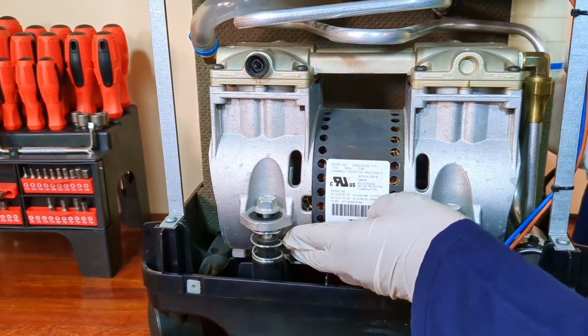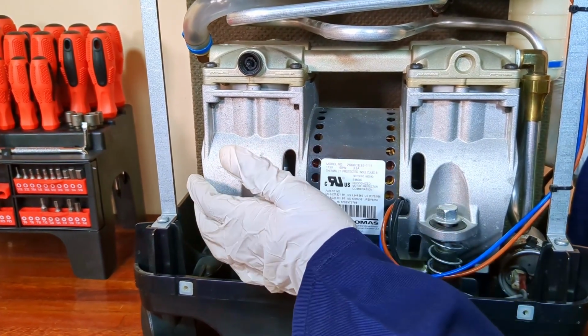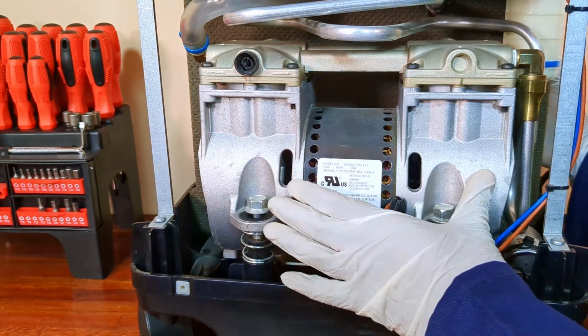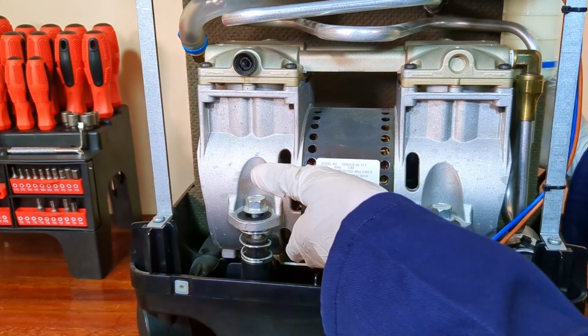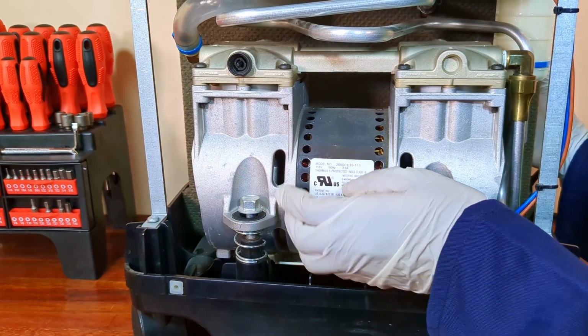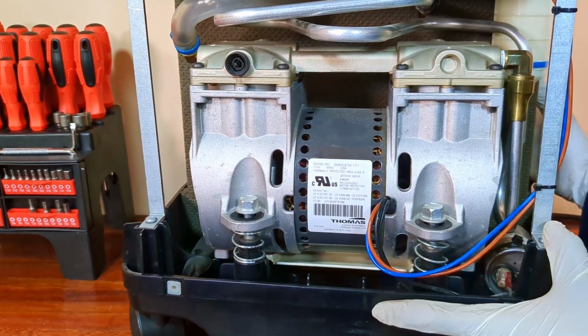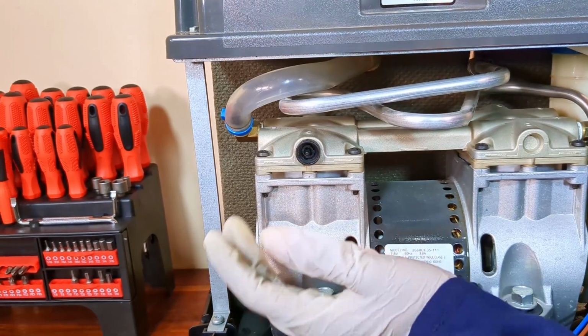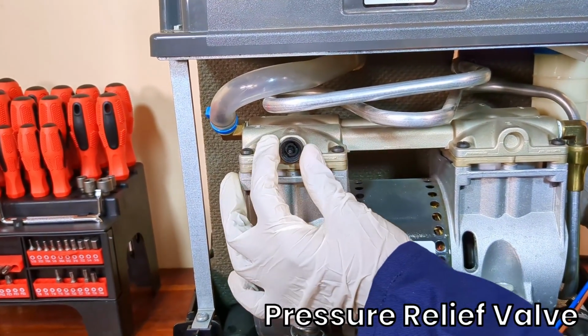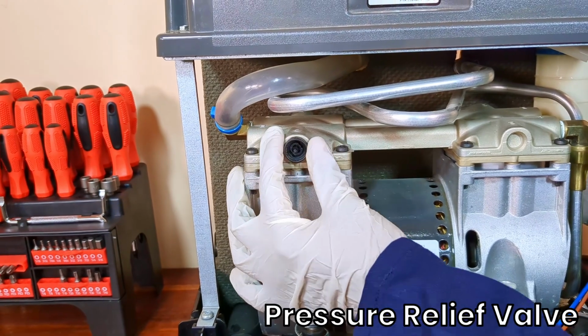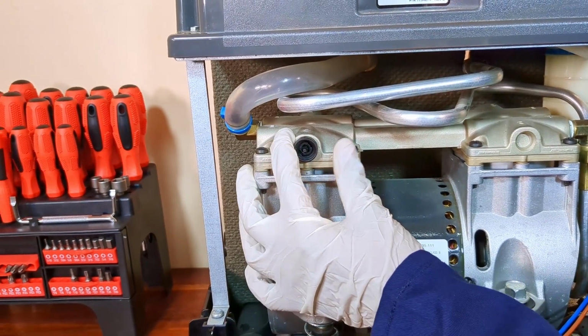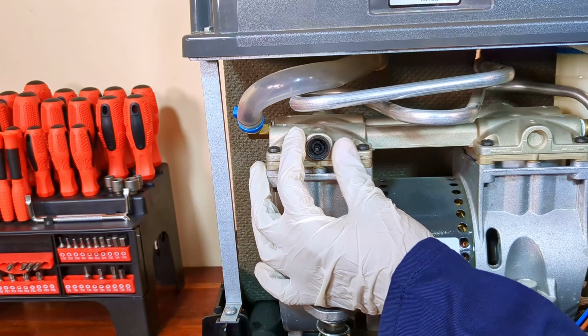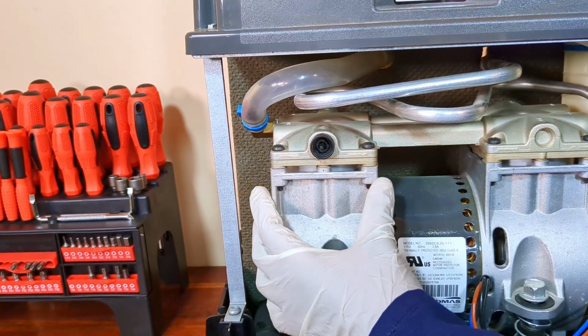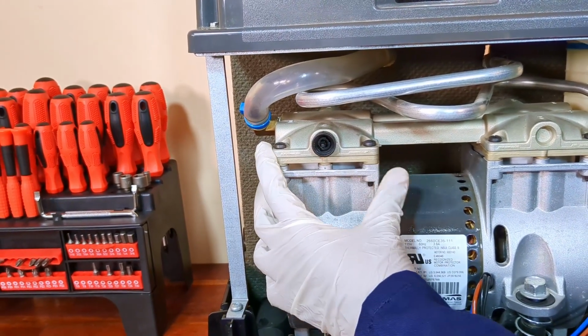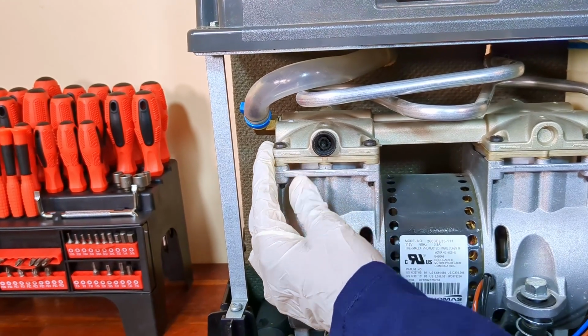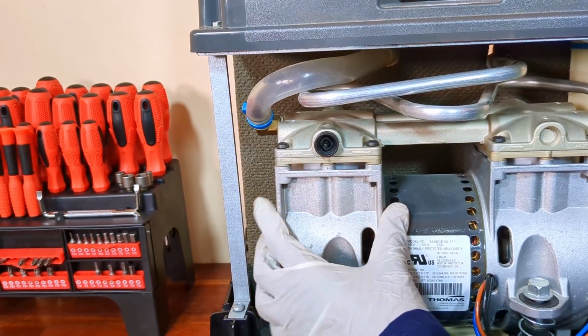The compressor has a voltage rating of 115 volts AC at a frequency of 60 Hz, and it also has a current rating of 3.8 amps. This is the pressure relief valve. This valve is fitted to the compressor and it pops out whenever the pressure exceeds the required pressure. And it is preset at 35 psi with a tolerance of plus or minus 3 psi.